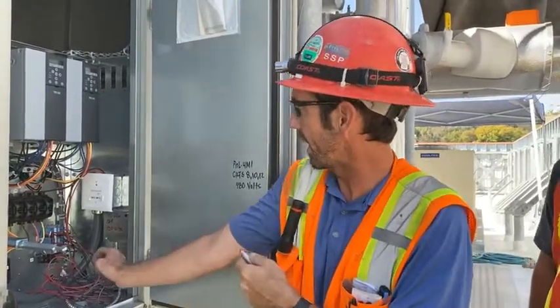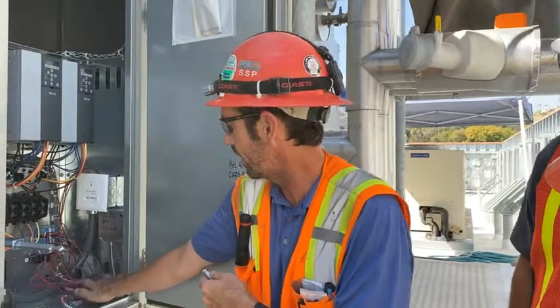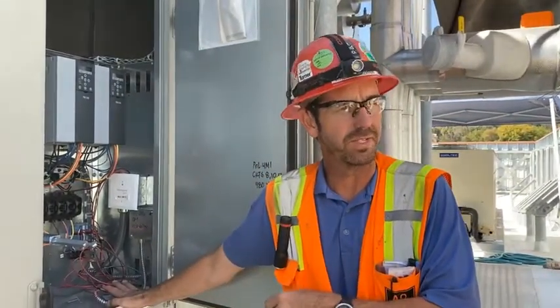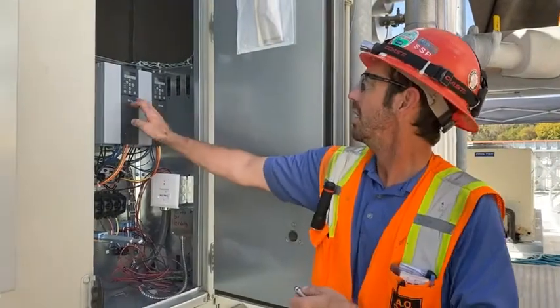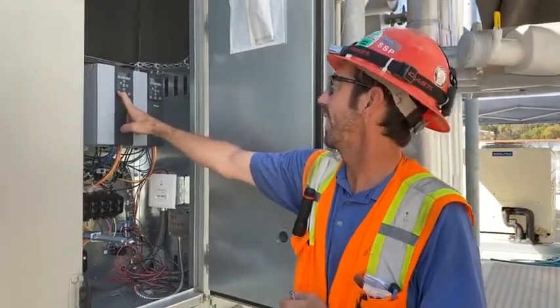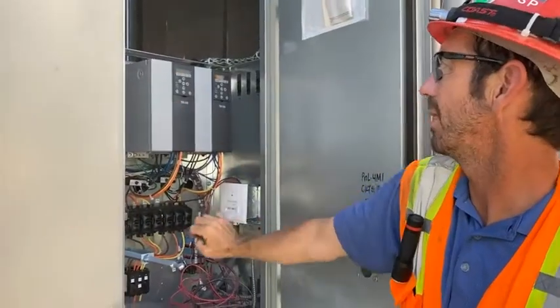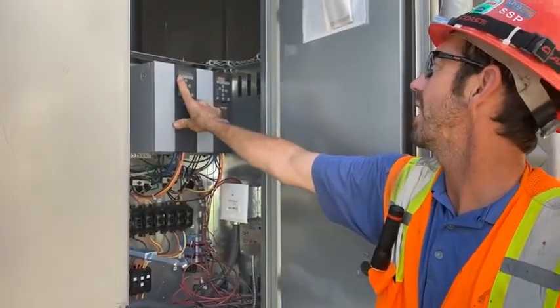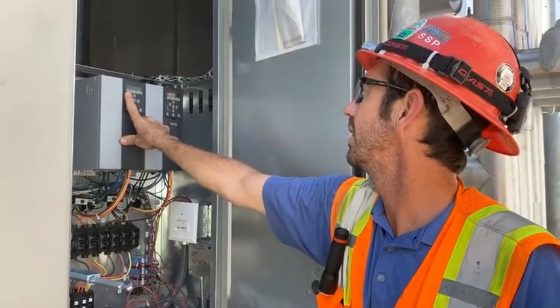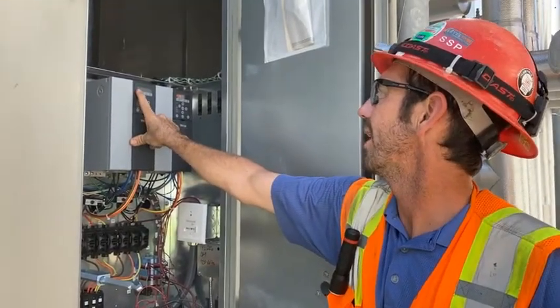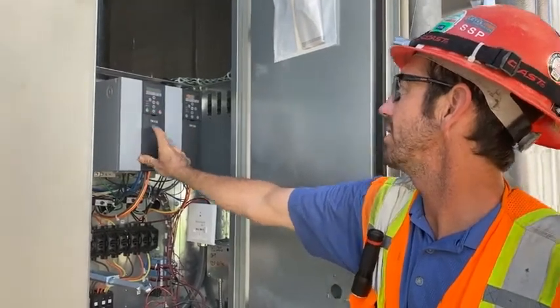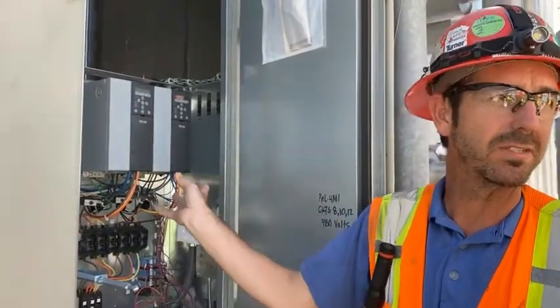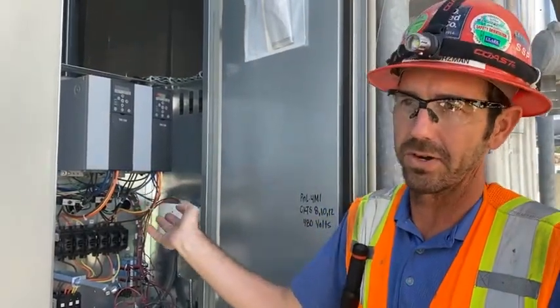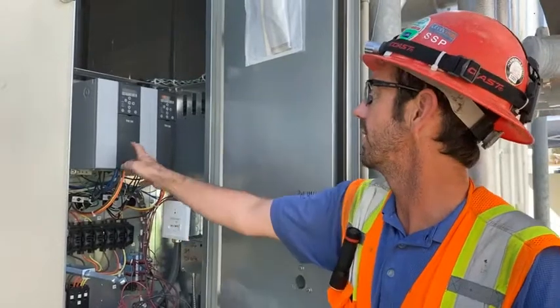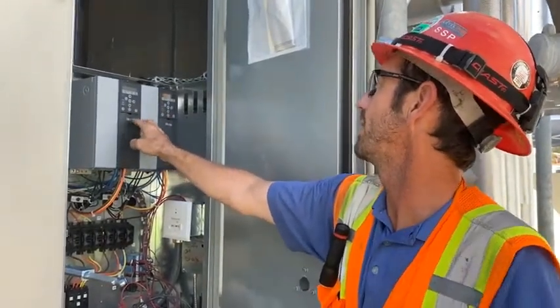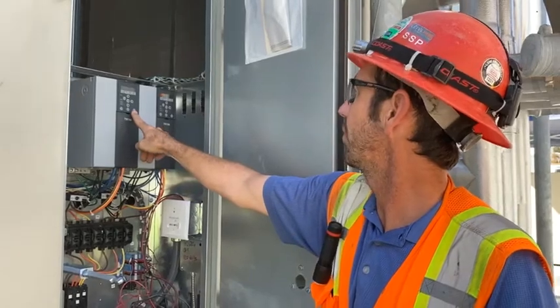What we'd also have to check is these wires, black and reds, coming up into the unit. These are your fire shutdown wires. That's another reason the unit cannot be working. So an easy way to check this would be just press hand. As the unit tries to turn on, it's not going to be one of those external safeties. So right now it tried to turn on, and it looks like it should be, it's starting to ramp right now. So 3 hertz, 4, 5, 6. So we know it's not a safety switch circuit that's keeping this unit off. It's probably going to be the controls guy. Okay. Again, they're finishing their integration into all the units. I press off to turn it back off. It's going to ramp down. But again, we want to keep these in auto.